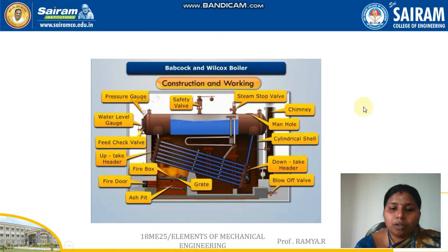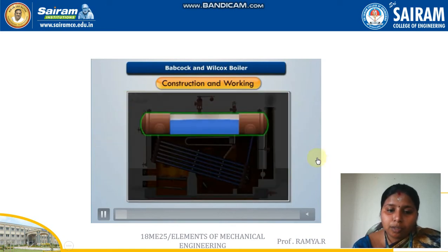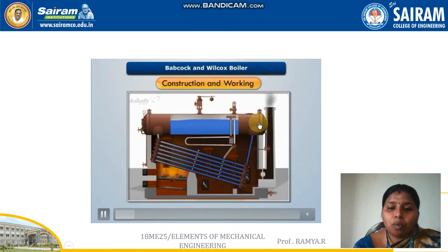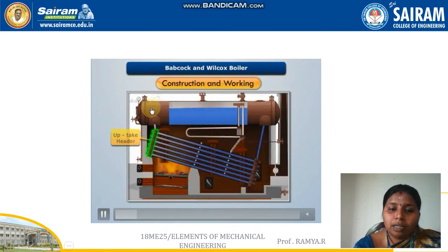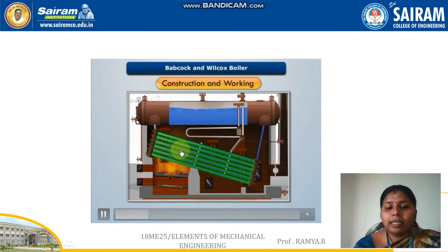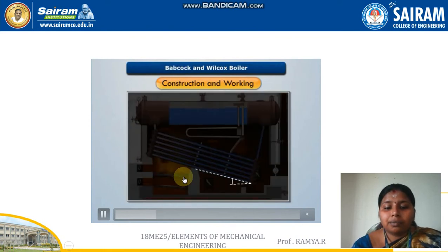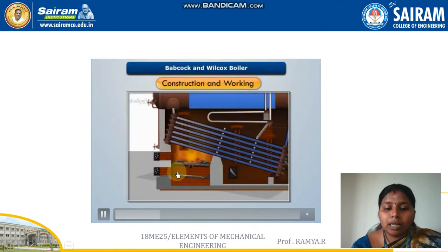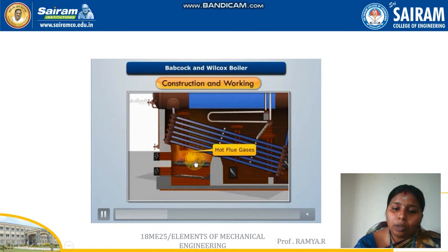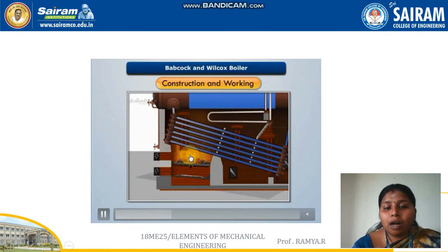This is the construction and working of the boiler as shown in the video. The boiler drum is filled with water and a water level indicator checks the water level. Through the downtake header, water enters the inclined tubes — placed at 10 to 15 degrees. The externally fired furnace burns solid fuel — coal — producing hot flue gases that pass through and around the tubes, heating the water.